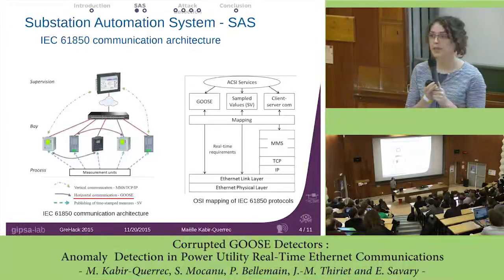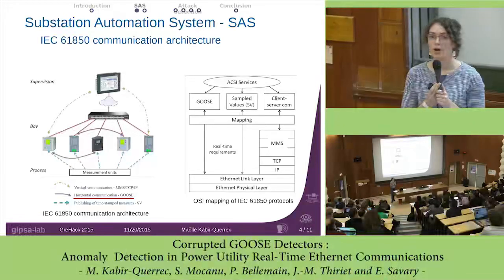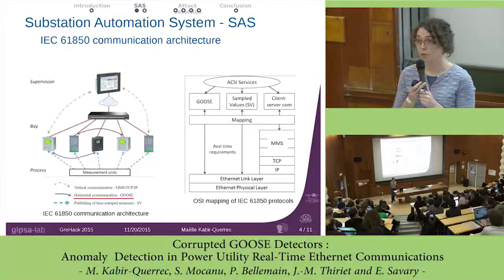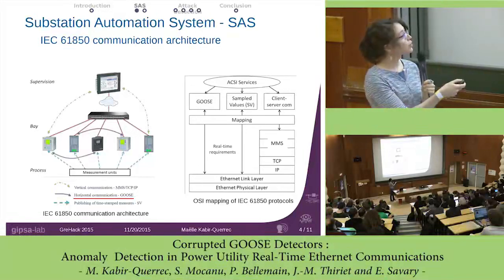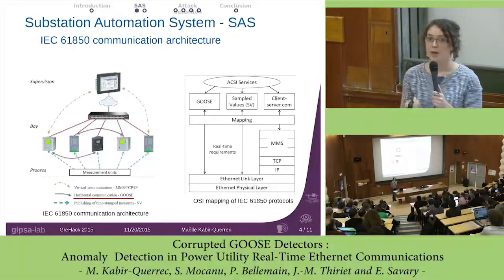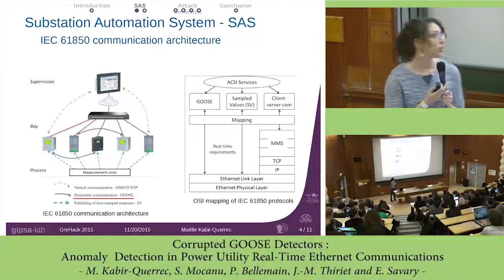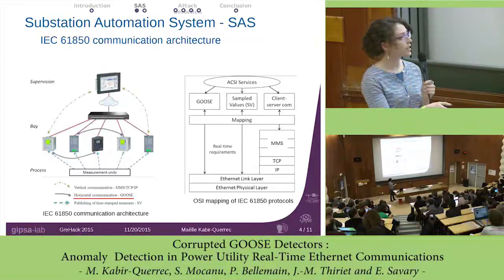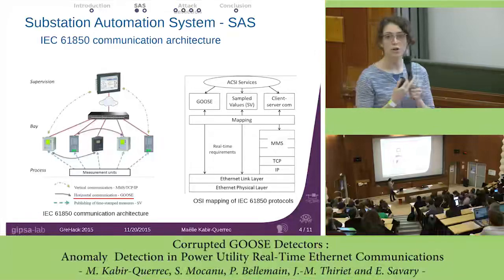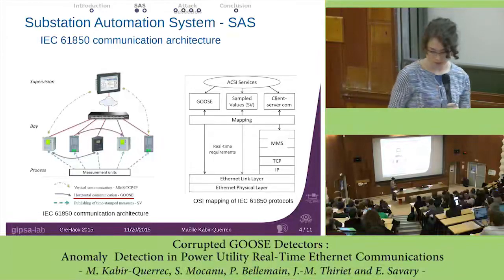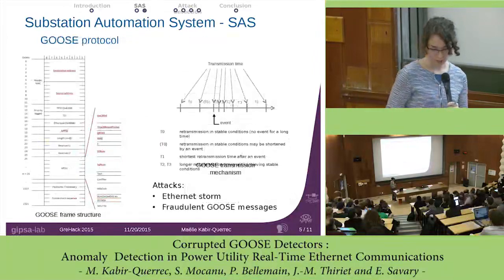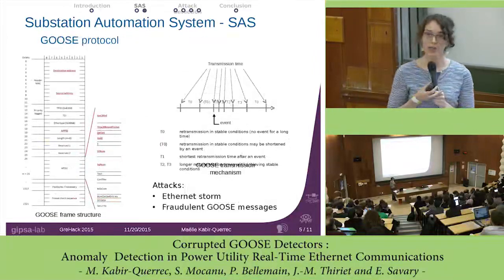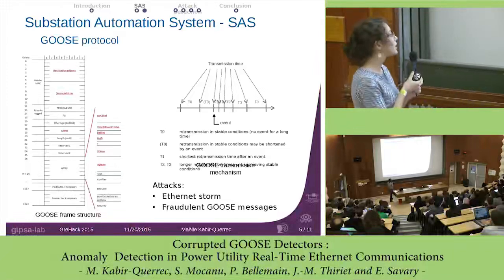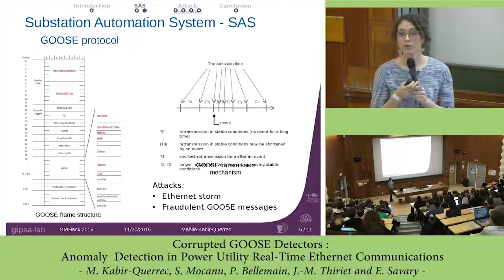GOOSE and Sampled Values are multicast protocols because they have strong real-time constraints. For example, the GOOSE protocol end-to-end transfer time must be less than 4 milliseconds. This is why it is directly mapped on the Ethernet link layer. But MMS is based on TCP/IP because there are no such real-time constraints. Okay. The GOOSE frame structure is standardized. I give it here to you. I will just detail the fields that are interesting for us.